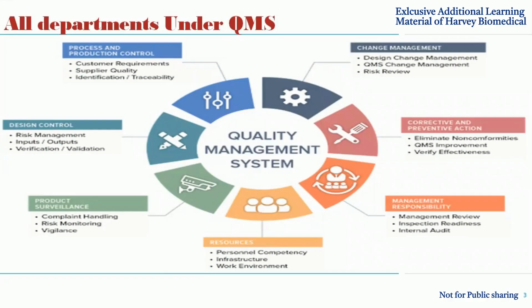Every time they go with an upgrade, the upgrade also involves non-conformities and also involves change management. It means they are making it effective, and they are upgrading your device for performance and safety, and to avoid the bugs or any non-conformities available in the software. They are eliminating those. And for QMS improvement also, if anything is improved in your device performance, risk, or safety, for that improvement they upgrade the software and verify the effectiveness.